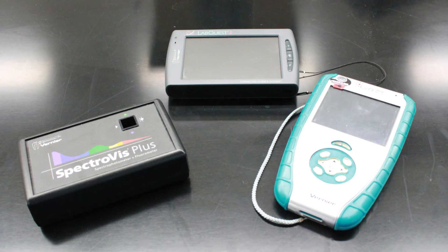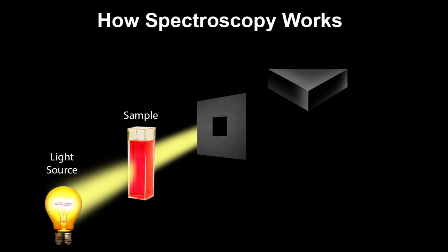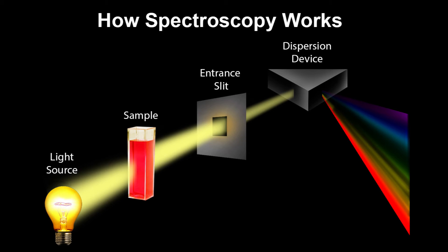In the undergraduate lab, we use the SpectroVis to take spectroscopy readings for us. Here is how this device works. We start off with the light source. The light source is directed through our sample into an entrance slit. Once the light passes through the slit, it is sent to a dispersion device that spreads out the light in a spectrum to be analyzed by a sensor.